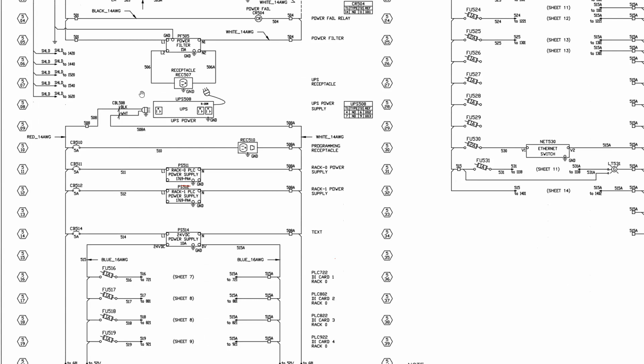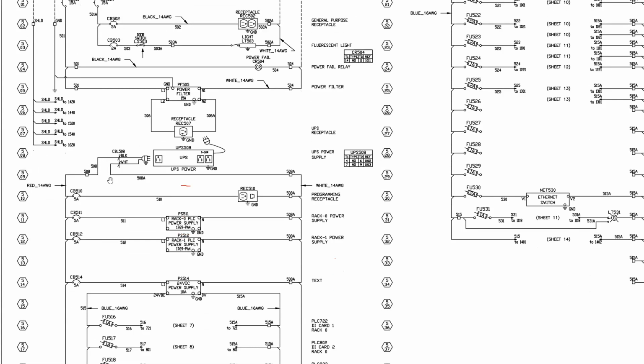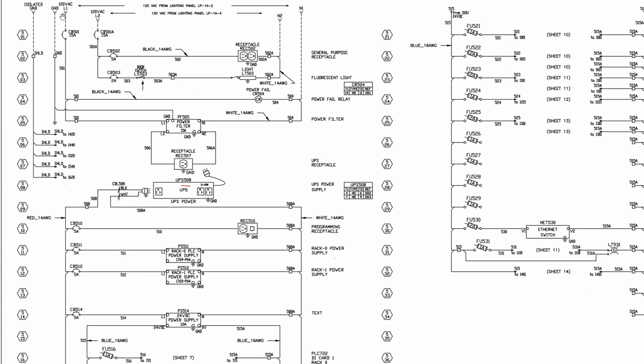So coming down, you'll notice this line is in line with L1, but it is not connected to it. That means it's being fed from the UPS, and these are not linked. So if you were to try to measure voltage from here to here, you might get a voltage from here to neutral, but I don't know.